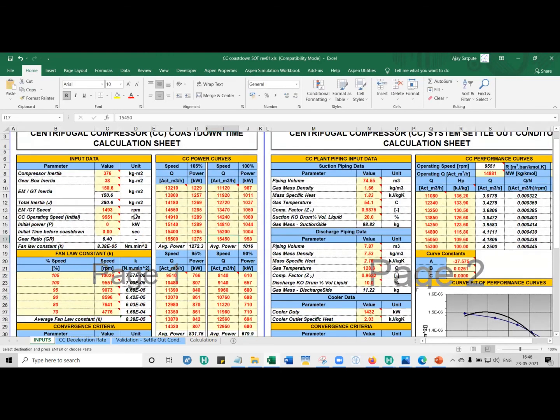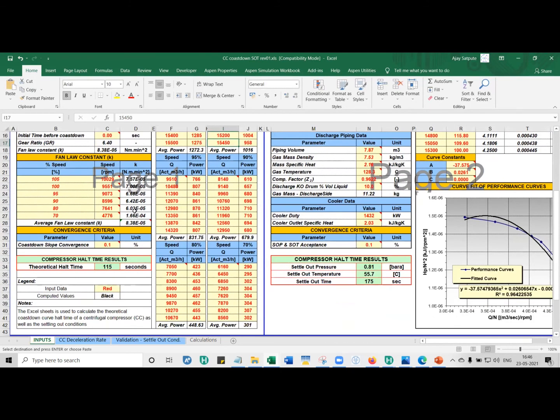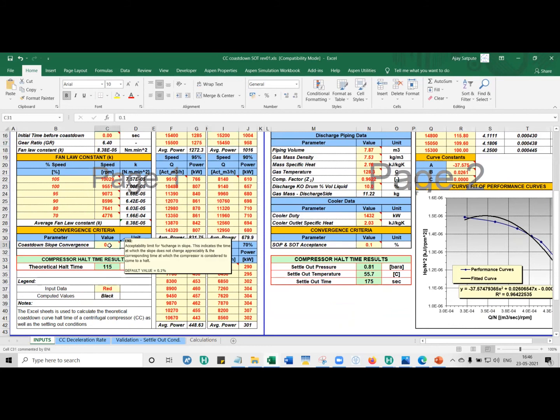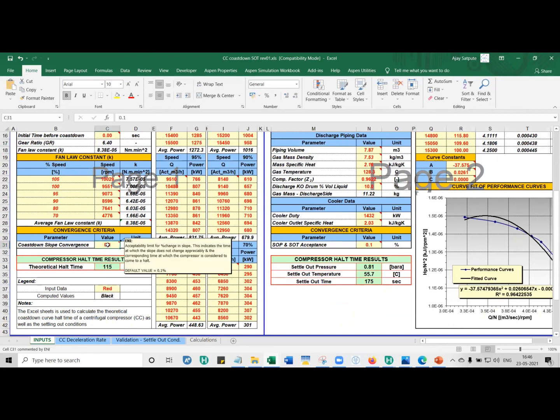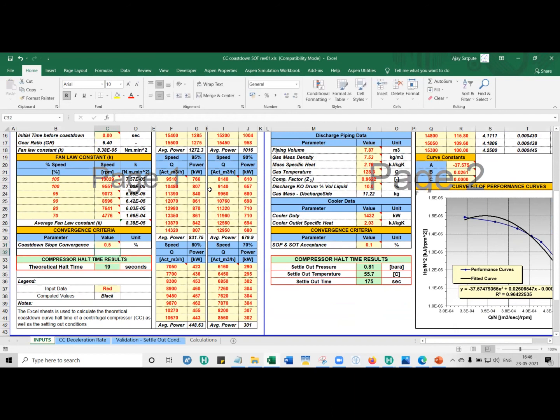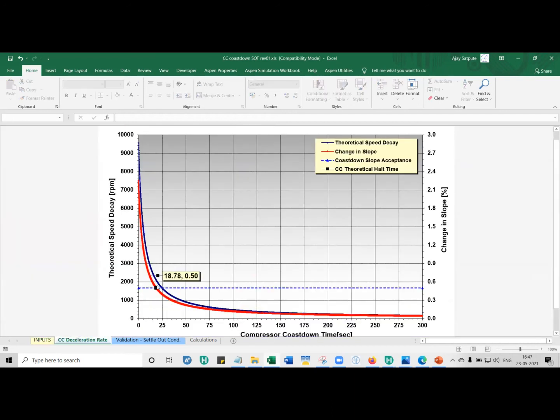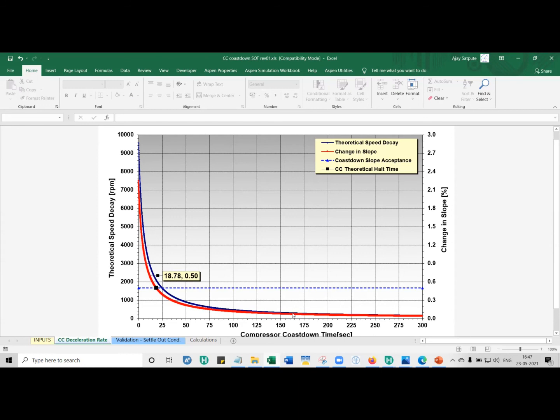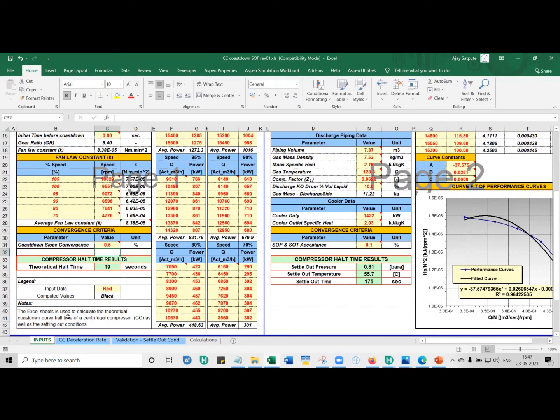So the way I have modeled that, you need some amount of field data to model this. I put a convergence criteria. In this case, when the difference in speed as it is coasting down is not more than 0.1, it is fine. So suppose let's say I put 0.5 instead, then it comes down even faster. But this is not realistic. But somewhere here it looks like the speed is coming to total halt. The red line is the change in slope. When the change in slope is not changing so much, in reality I don't have that. The curve will slowly go to 0 here, but this curve mathematically goes to 0 only at infinity.